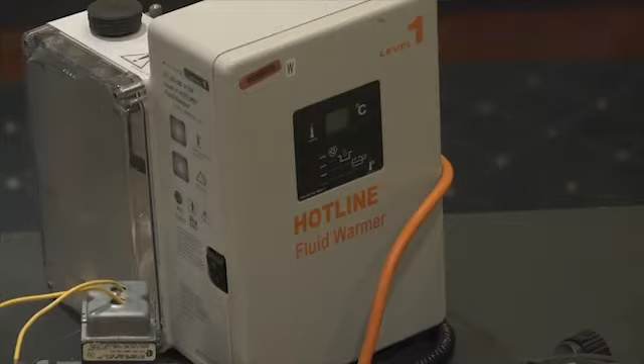One time a year, we plug in a hotline box and we hear a loud, audible, persistent alarm, and that's our line isolation monitor. It's different from all of the other alarms that we hear in the operating room, so the question becomes, what do we do? The answer is, undo what you just did. That is almost always unplug the hotline box, the fluid warmer, and remove it from the room. But what we see in the operating room is no interruption in power. But because of the standards that we just talked about, it is no longer an obligation to have an isolated power system in an operating room.